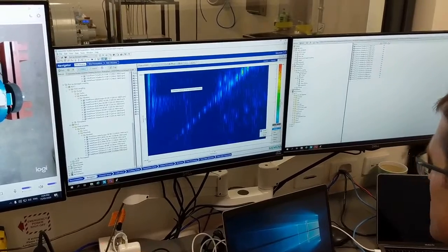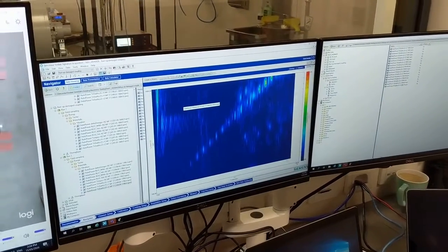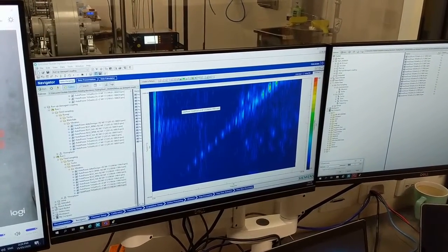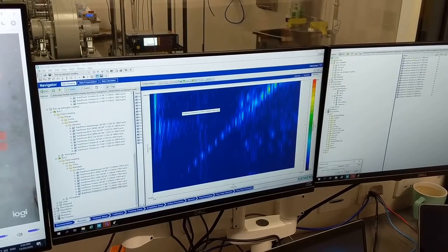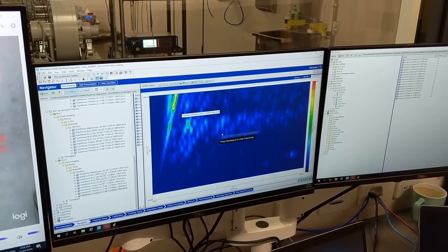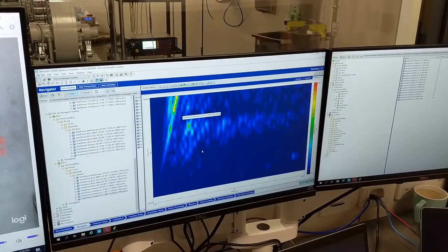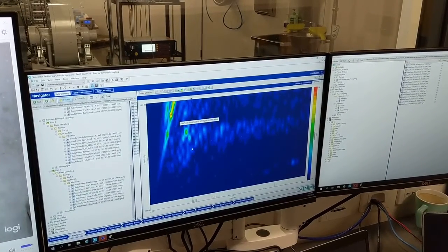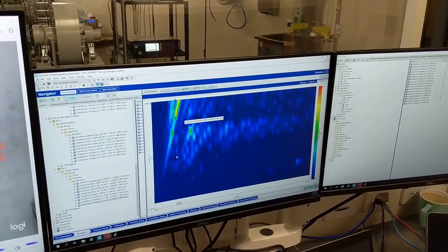And so if I change the x-axis to 256 Hertz, you can quite nicely now see here, if I put a single cursor on the x direction, we believe that there's a resonance around about 31 or 32 Hertz.